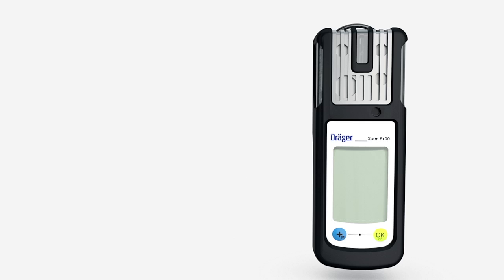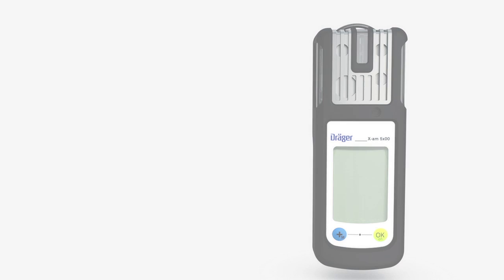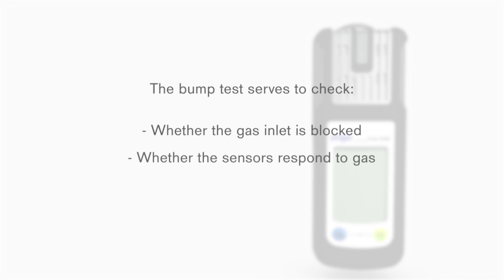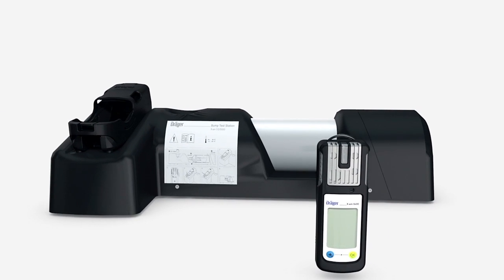Depending on the regulations or guidelines, you will first need to perform a function test of your Dräger X-am 5000 or Dräger X-am 5600. The bump test serves to check whether the gas inlet is blocked, whether the sensors respond to gas, and whether the alarm elements are triggered. To do so, insert the device after turning it on.